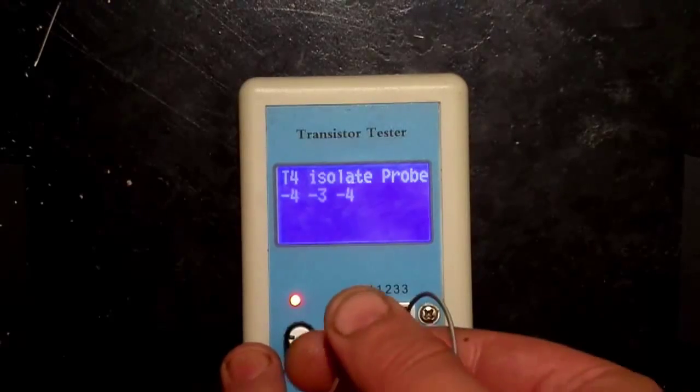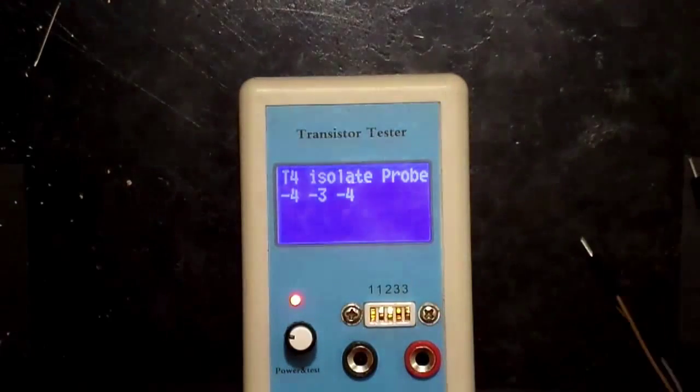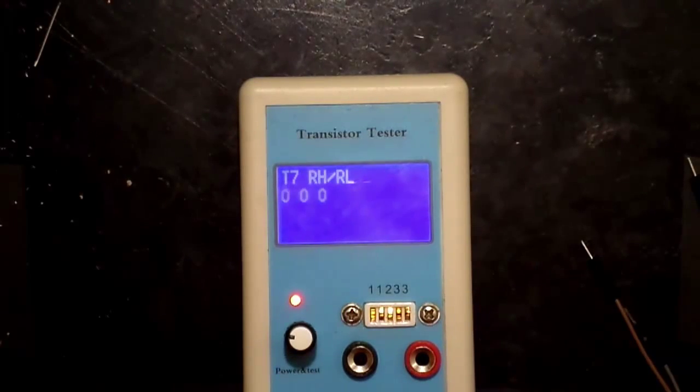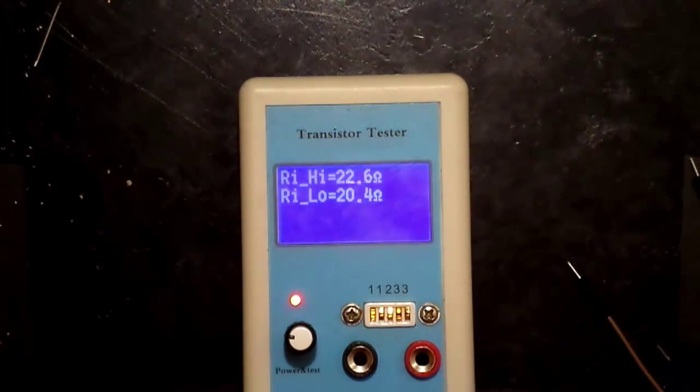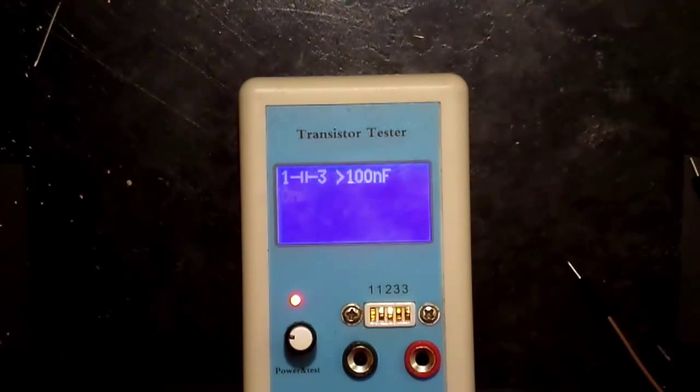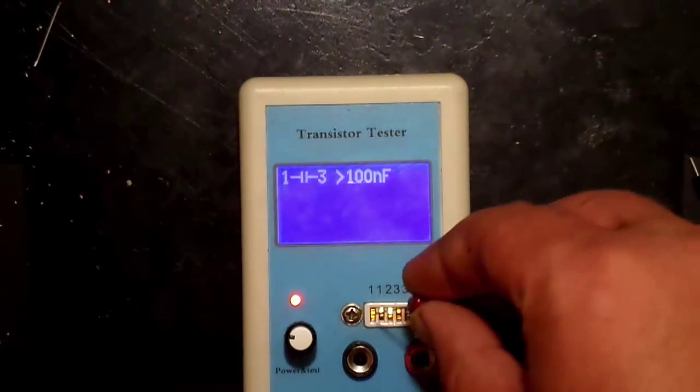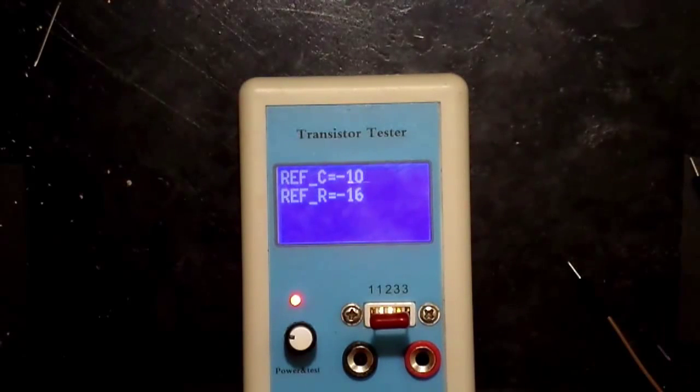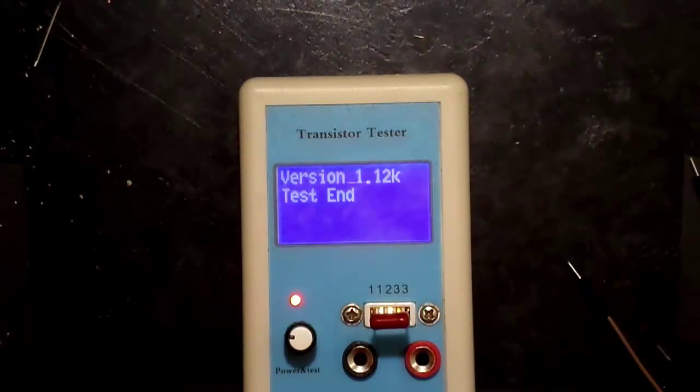At test 4, remove the wires. When you see this message, insert the large ceramic capacitor you got with the kit, or any ceramic capacitor that's higher than 100 nanofarad. And that's it, the calibration is now completed.